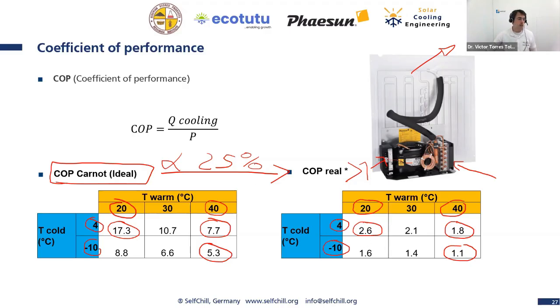I can tell you that air conditioning, for example, quite often works at an efficiency of 400%. Why? Because the ambient temperature, for example, at night is only 25 or 30 degrees, and the cooling is happening at 15 or 20 degrees. So the delta T is so small that the compressor doesn't have to work so much, so the COP goes higher, up to 4.